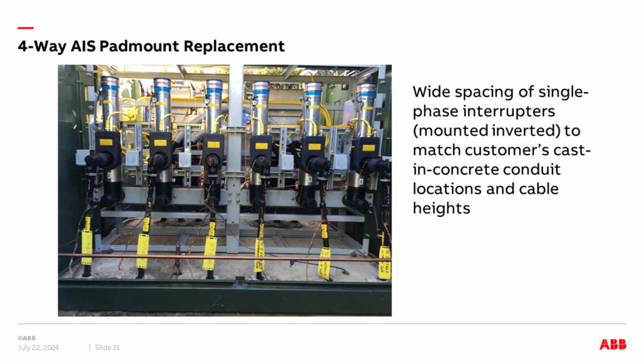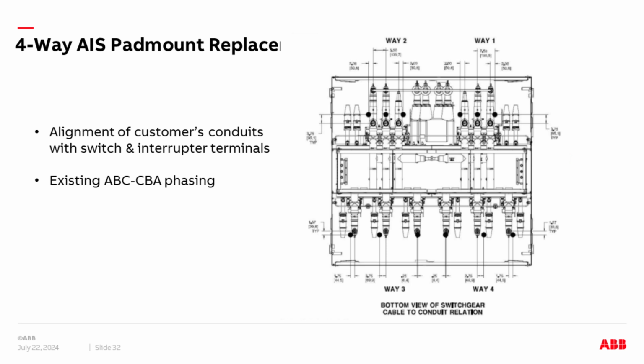In the four-way job, here we see the single phase. Each way had three single phase interrupters, which had to be spaced quite far apart in order to match up with these cable locations. That's why it looks so spread out, but they were already spread out on the existing gear, again with ABC to CBA phasing. In this engineering drawing, the black dots represent the existing locations for cables that had to be matched. And this is a couple of source ways on the top and the three single phase each on the load ways on the bottom.